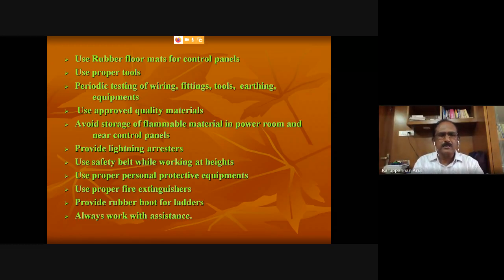Use proper fire extinguishers. The common types are foam or water type, but for electrical fire we should not use these, because water conducts electricity. We have to use CO2 (carbon dioxide) extinguishers or DCP (dry chemical powder). If the fire is on the ground or on flammable material, dry chemical powder can be used. For sophisticated equipment like computers, servers, or electronic items, only CO2 should be used, since DCP will harm the circuits. So we must use CO2 or DCP fire extinguishers for electrical fires, and we should know this well.